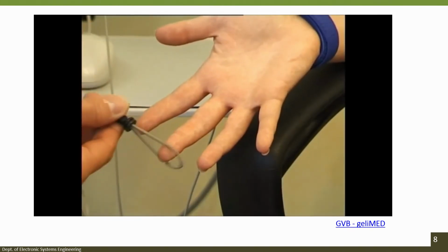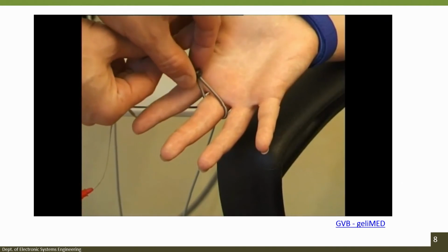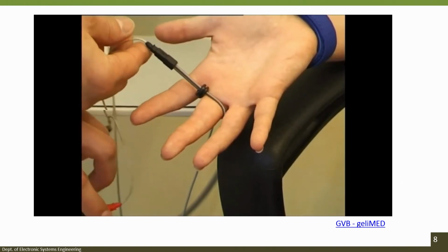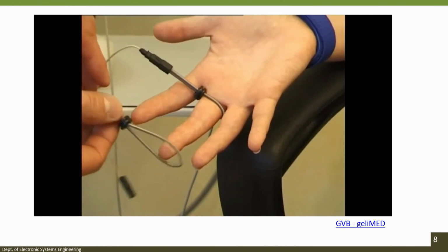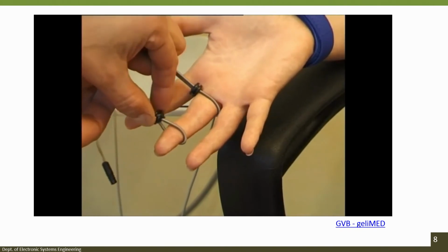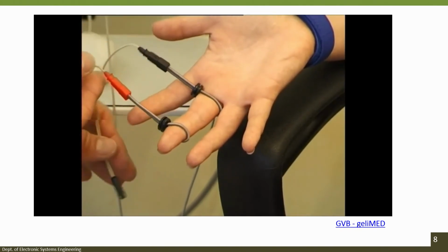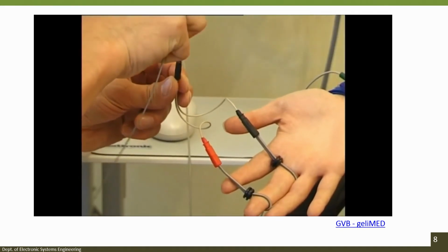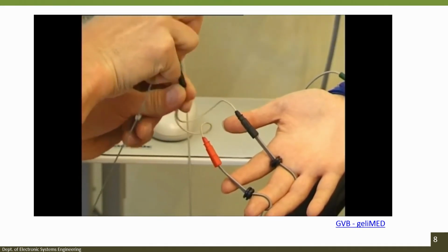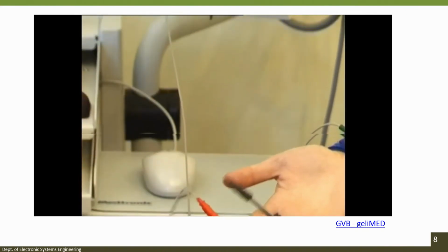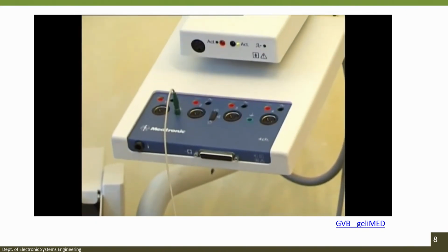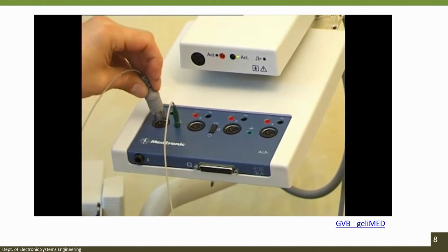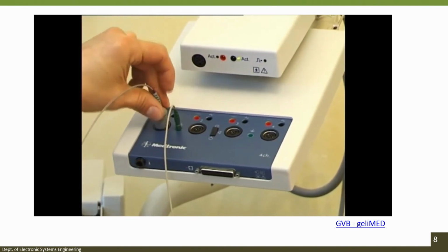The antidromic method shows the second variation of sensitive neurography. In this case, digital ring electrodes are used as recording electrodes. The active electrode is attached proximally and the reference electrode attached distally in this method. These electrodes, which are also parts of the multifunctional system, can be connected to the EMG instrument by the multifunctional cable.